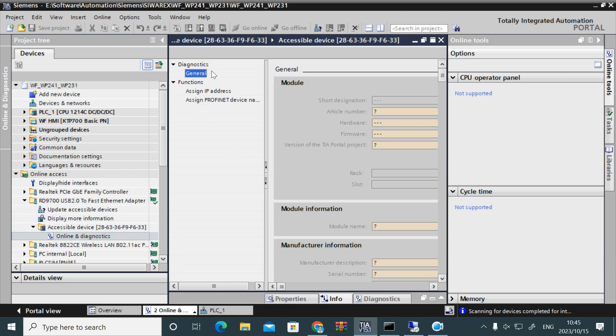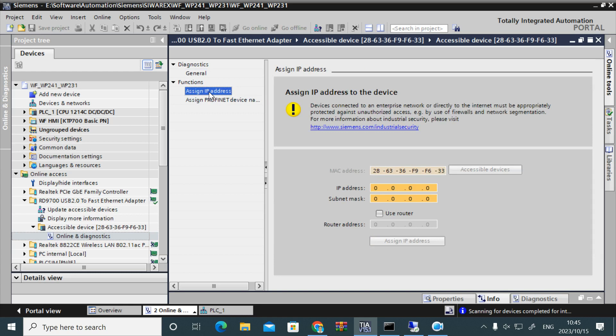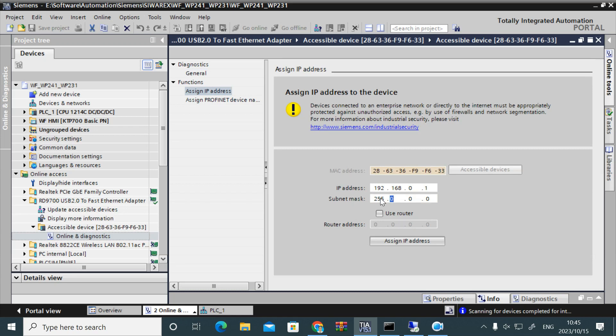The device shows limited parameters because it is connected by Ethernet ISO, not Ethernet TCP/IP. By Ethernet ISO you can access only a minimum set of parameters. To set the IP address, click on 'Assign IP Address.' Enter the IP address from the project, and set the same subnet as the project. Now click 'Assign IP Address' to apply it.